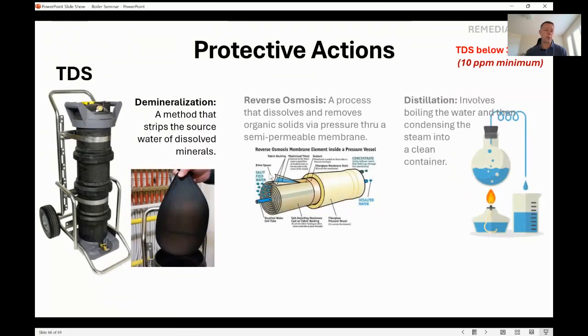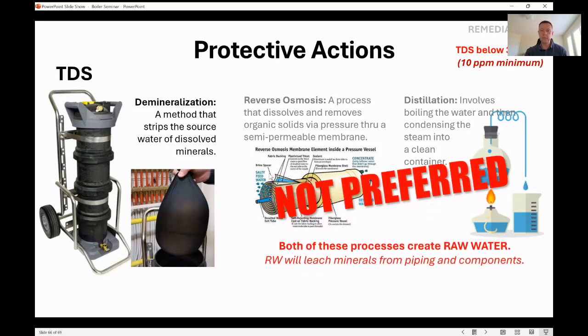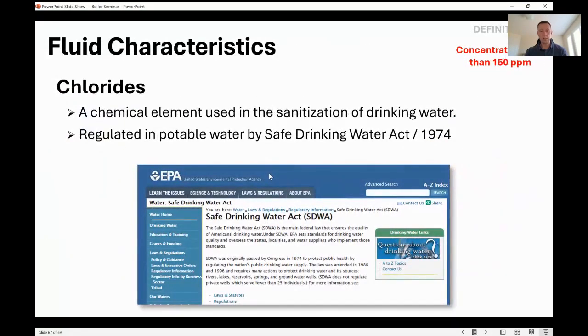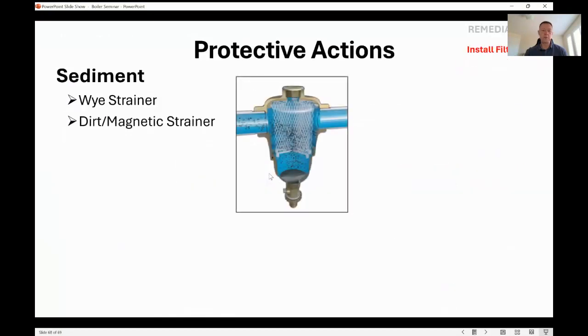Always, when you're putting in quality water originally, I recommend demineralized water. Don't put in RO or distilled water, because those waters tend to be like raw water. They're very aggressive. They want stuff. So basically, they're going to be pulling different stuff out of your system to put into the solution, because it has nothing in it. So go with the demineralized. As I said, chlorides, always be conscious of them.